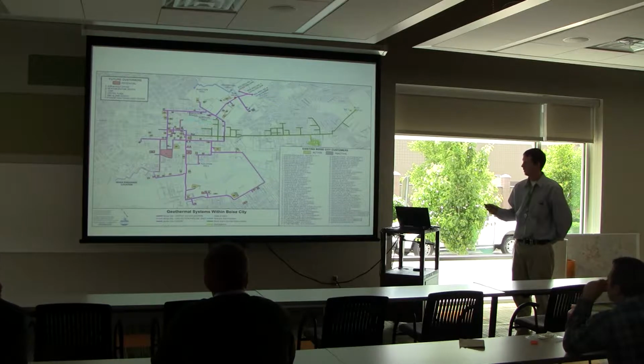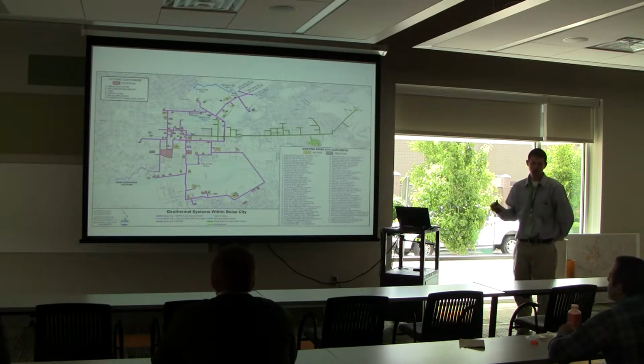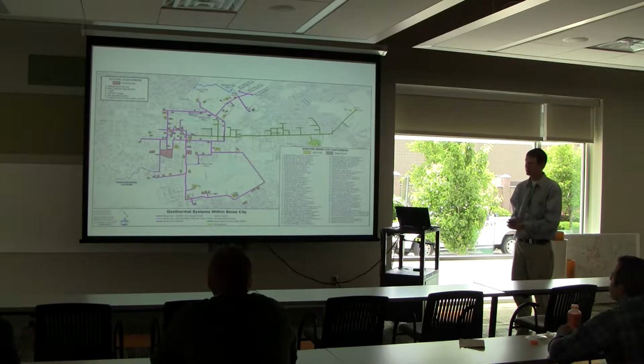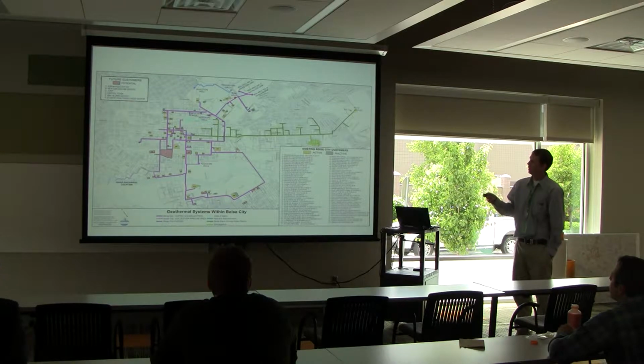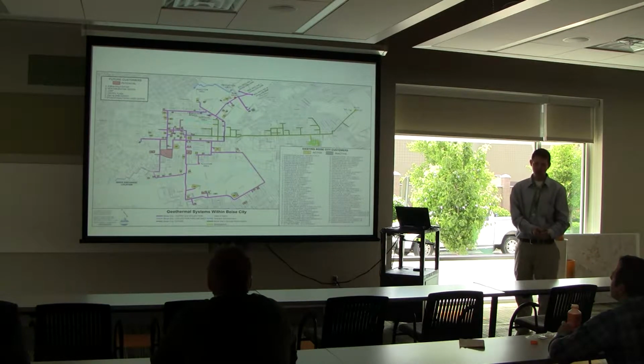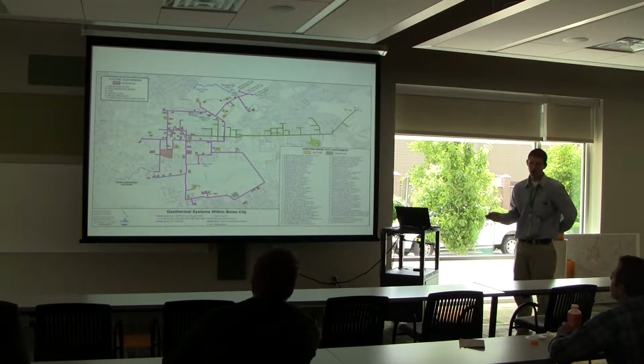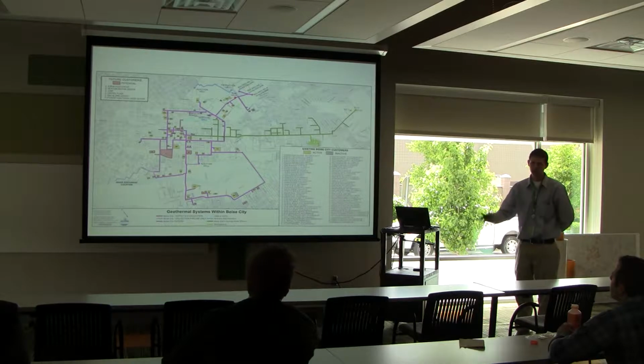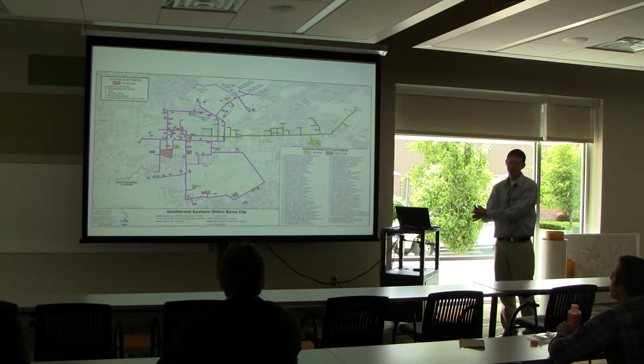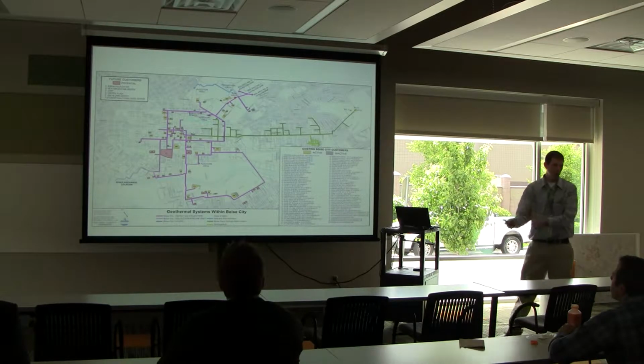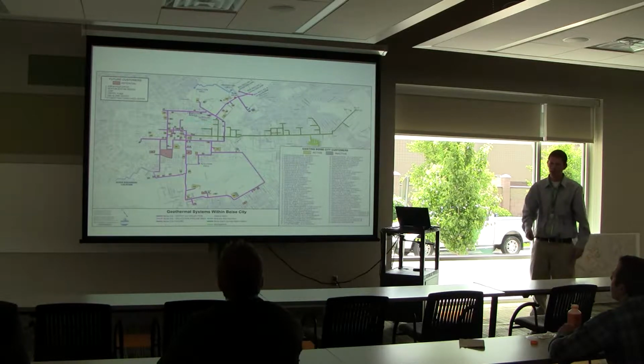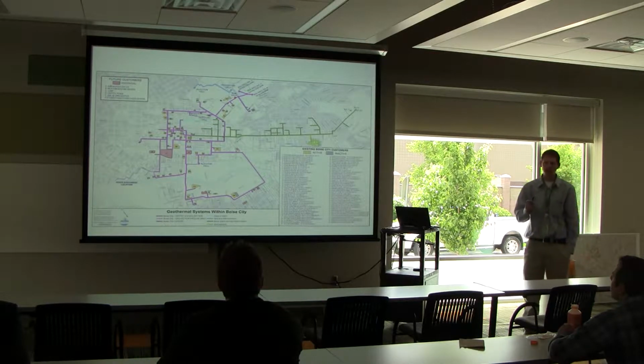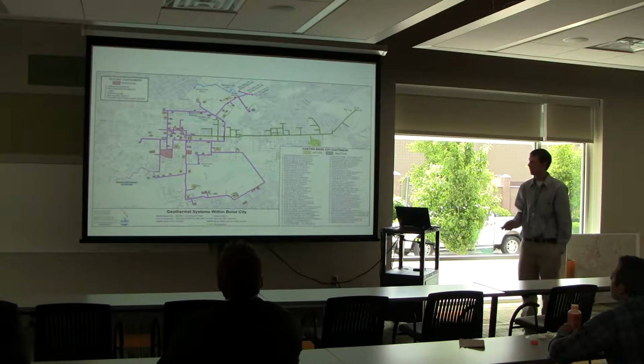All these systems use the geothermal water primarily for space heating. These 3 though, the VA, the state, and mine, use a supply injection system. Everywhere you see a line on our system, it's actually 2 lines: a supply line taking hot water to a building, where the heat's extracted out of the water, then we collect the water through another set of pipeline and take it to an injection well. We re-inject every gallon that we pump out.